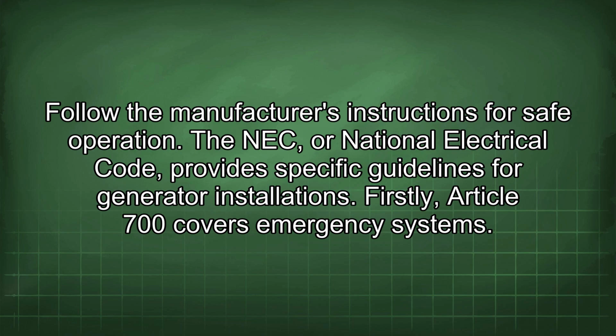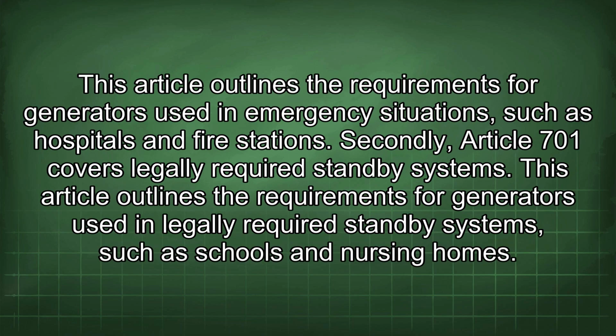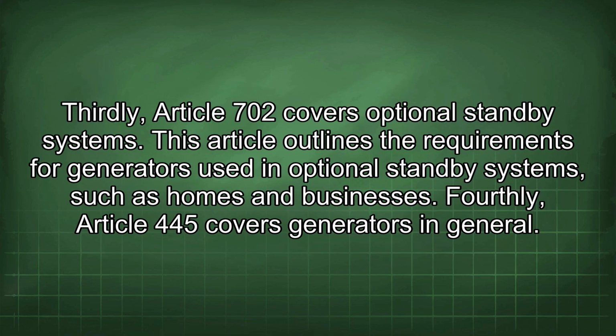The NEC, or National Electrical Code, provides specific guidelines for generator installations. Firstly, Article 700 covers emergency systems. This article outlines the requirements for generators used in emergency situations such as hospitals and fire stations. Secondly, Article 701 covers legally required standby systems. This article outlines the requirements for generators used in legally required standby systems such as schools and nursing homes. Thirdly, Article 702 covers optional standby systems. This article outlines the requirements for generators used in optional standby systems such as homes and businesses.